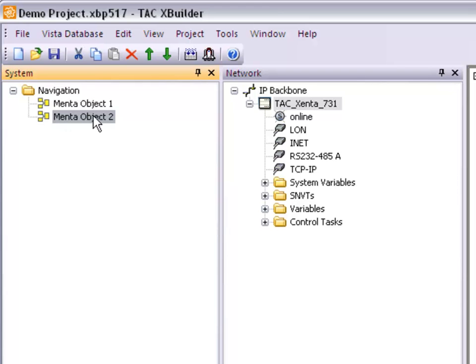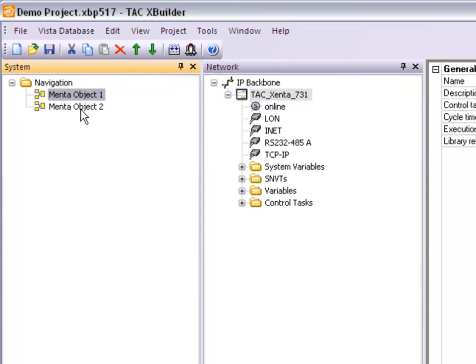So you can have one program containing an air handling unit and another one containing a zone, for instance. So do consider that before making a project, that you might need to reconsider how you do your programs, dividing the programs up into different parts with different functionality, and not making one large program with everything in it.